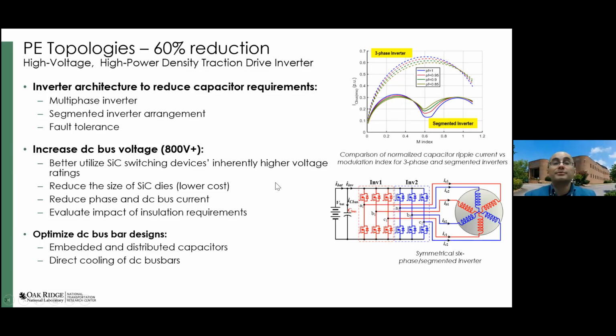Another advantage of these segmented inverters is that it almost looks like a 6-phase system, a 6-phase motor. This doesn't mean the motor is more complicated - you just have to make two sets of 3-phase windings. Instead of connecting them internally, you're connecting them to the inverter, and switching them through the inverter. This system also allows more fault tolerant operation.